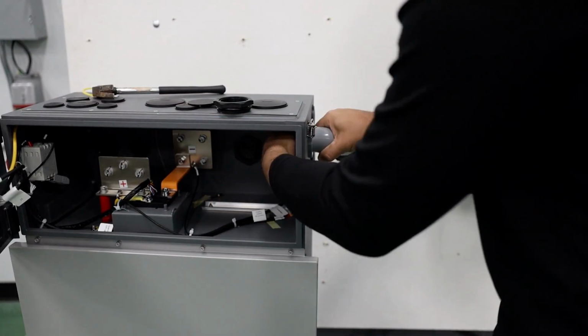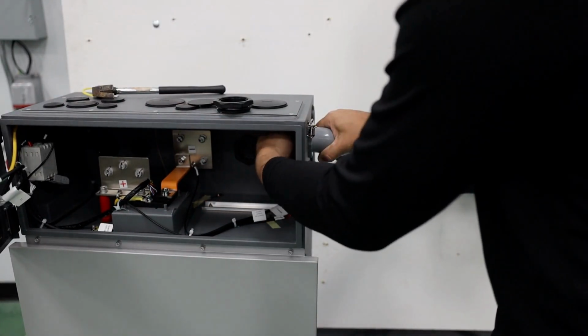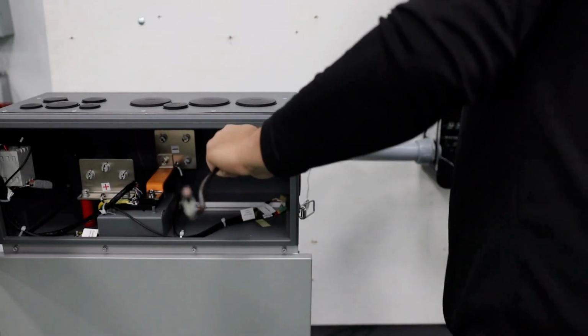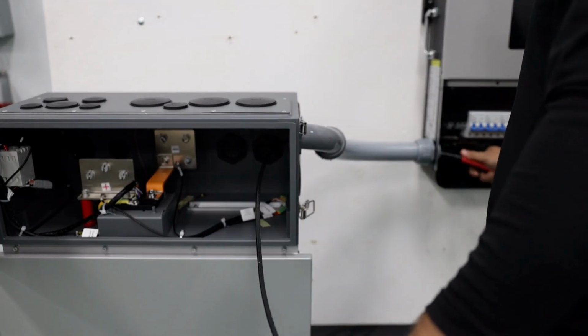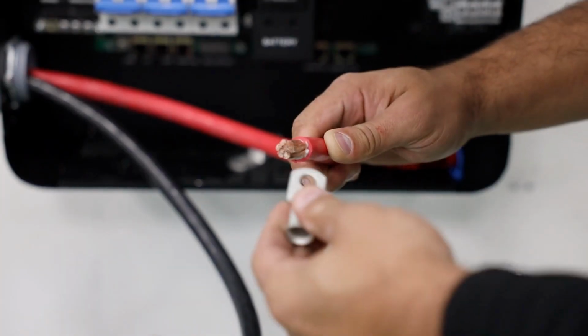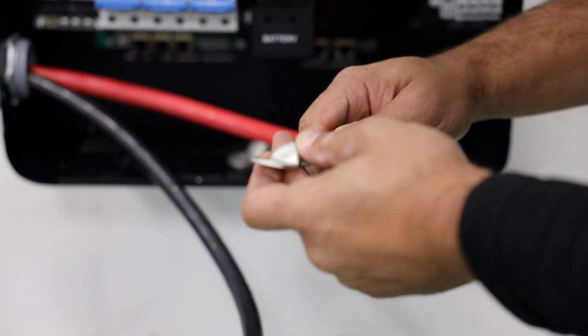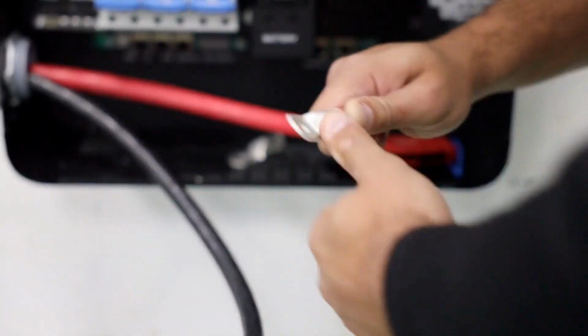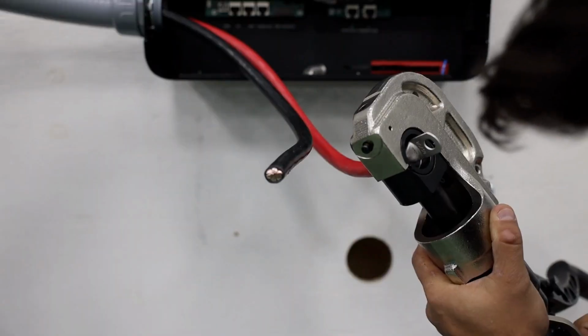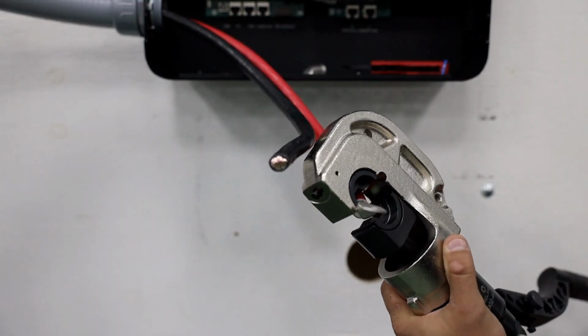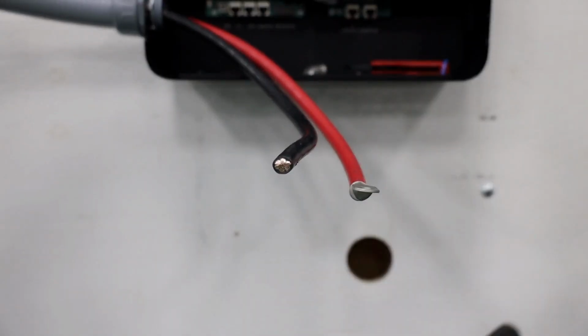Secure all conduit fittings, then route a pair of 2-aught battery cable along with a communication cable through the conduit. Next, strip the cable and add a 2-aught lug terminal with a 1/4 inch ring size on the inverter side and 3/8 on the battery side. Crimp and put electrical tape around both the lug and the cable for proper termination.